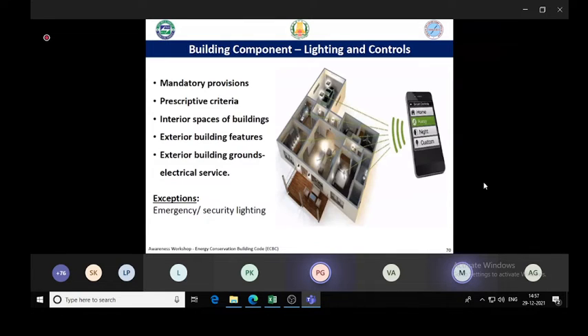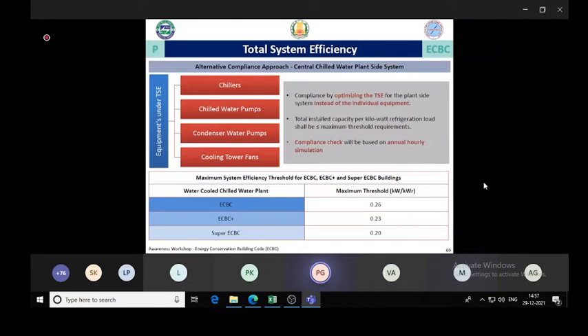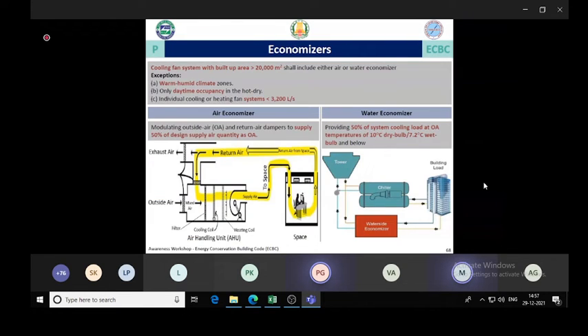Okay. Now, in prescriptive requirements, the code also specifies minimum efficiency for the HVAC systems like pumps, chilled water pumps, the cooling tower fans, and the air handling units. So for all this, there are minimum efficiency requirements such as pump efficiency. It has to be more than 70%. AHU fan efficiency should be more than 60%. As well as the motors used in the AHUs and these pumps, they need to be at least IE2 specified. IE2 efficiency or higher.